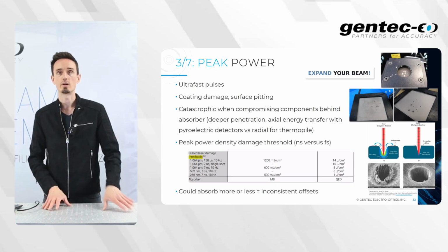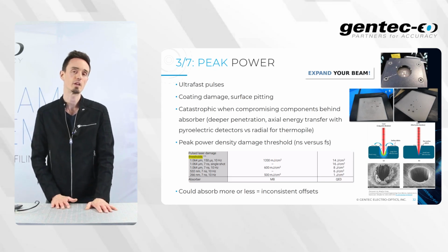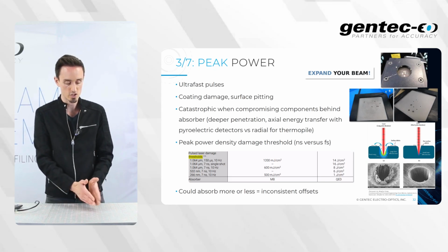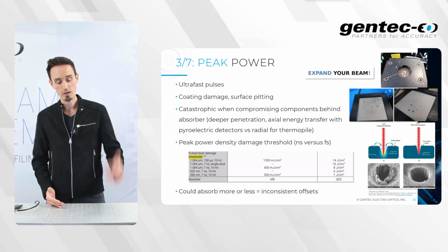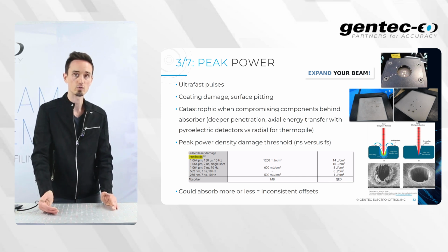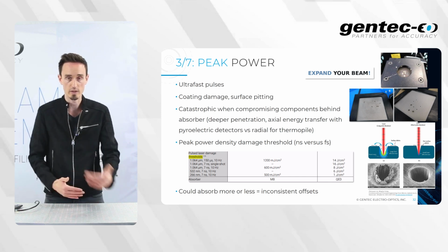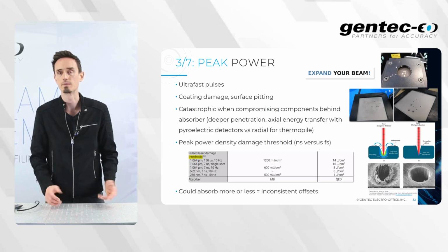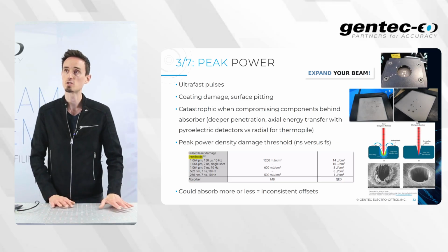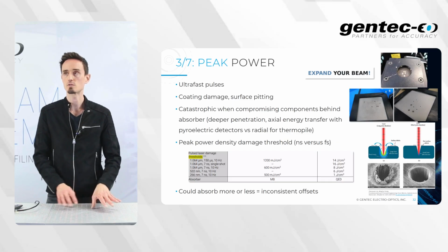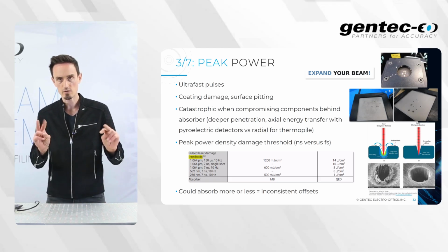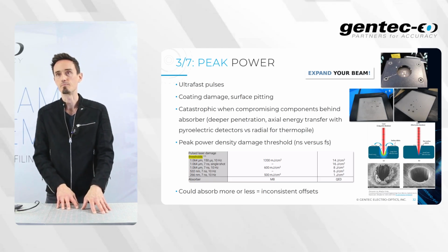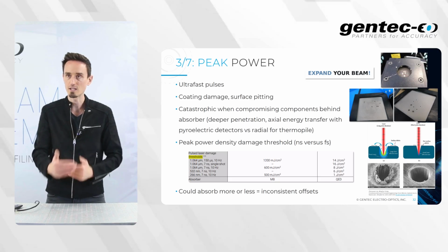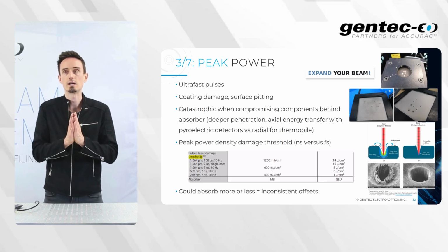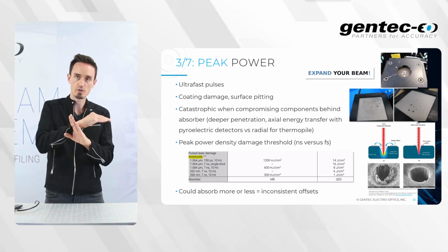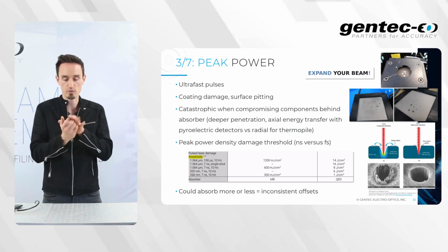Okay, peak power. So this is the realm of ultra-fast pulses. We all know that for the same energy level, a nanosecond pulse versus a femtosecond pulse won't have the same kind of interaction with the matter it is targeting. Typical damages here, as you can see, are coating damages and surface pitting. It is often catastrophic, in the sense that it compromises the components behind the absorber, because we're talking here about an axial energy transfer versus typically radial for thermopile.